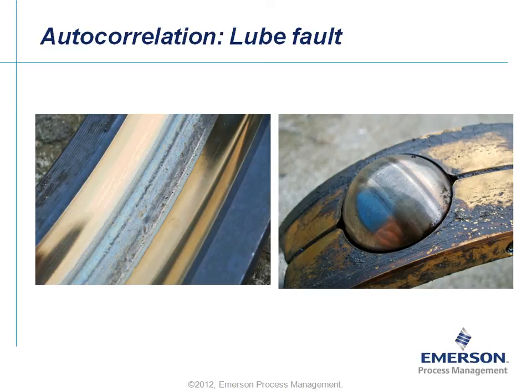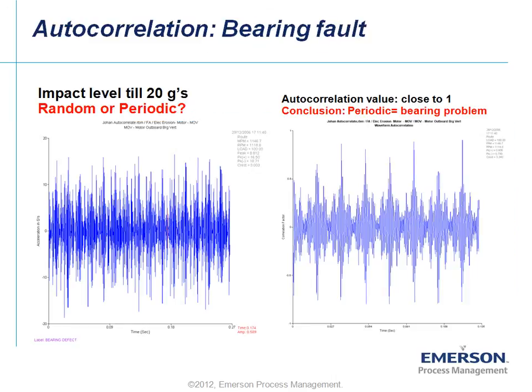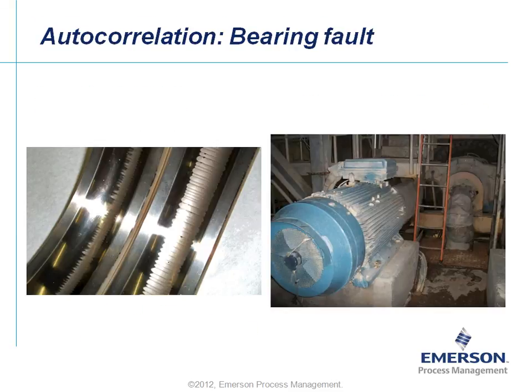These are pictures from the bearing where you can clearly see the lubrication problem. In the second example, we have a waveform with impact levels from minus 20 to plus 20, so also roughly 40 Gs. The question is again: is the data random or repeatable? If you perform the autocorrelation process on this waveform, you have impact levels in the autocorrelation result of roughly 1 — so very repeatable. And here is the proof: this was the bearing inside, and you can clearly see a heavily damaged bearing.